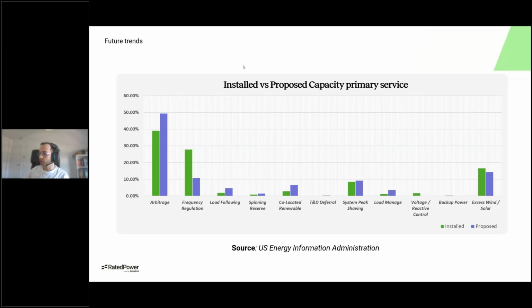Now for 2023, this is comparing the installed capacity against the proposed capacity for future projects. This is the primary service, so this means that it's the primary target of the battery system. So each battery system will only have one primary service here. And again, we see a shift towards arbitrage. We are seeing an increase from 39% to 49%. And we see that frequency regulation, despite still being important, might not be the most cost-effective solution or the most lucrative out of all of them. So yeah, we see a tendency towards arbitrage, and that's what we're seeing also in general in Europe.